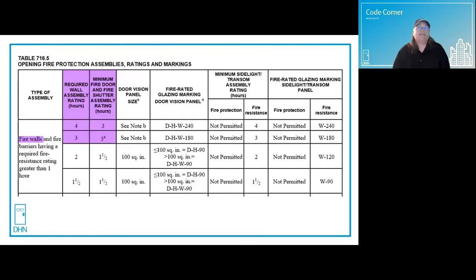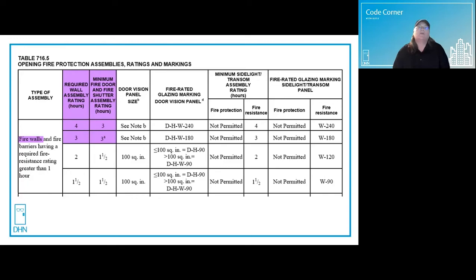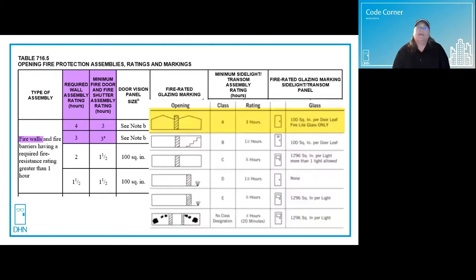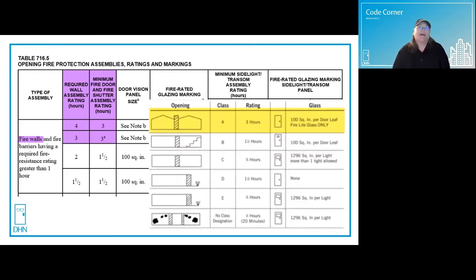IBC table 716.5 shows the fire protection rating for doors and firewalls as three hours. Firewalls are used to divide a structure into two separate buildings. The division must be vertical and go all the way through the roof. The image from NFPA 80 shows us that a three hour door is classified as A-labeled.